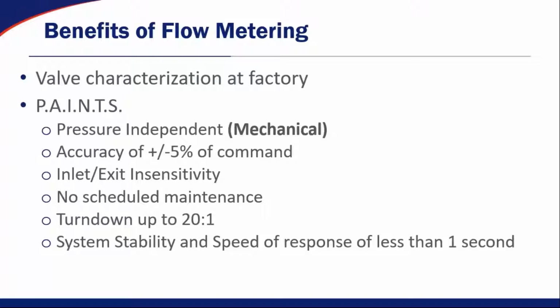So the benefits of flow metering as it applies to the Phoenix Controls valve, number one is that the valves are characterized at the factory. And that really gives you a couple of benefits. You don't have to worry about rebalancing these in the field. You don't have the guesswork of putting a K factor into the airflow control device once it's installed in the field.